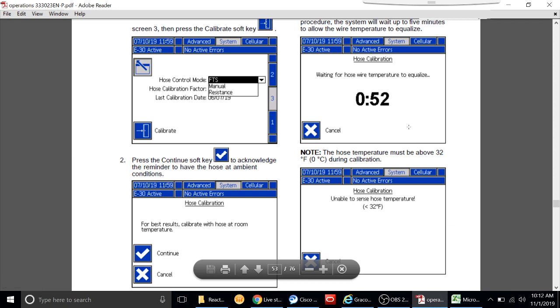You may see a window pop up here that gives you a countdown or a timer while the system is calibrating. But what happens if my system doesn't calibrate? What could be causing that? What would prevent me from running that? Well, a lot of times there's a connection within the hose that's not being made, whether it's an actual connection point or internally the wire wrap around that hose is broken. And if we're trying to figure out that value for the hose and there's no way of receiving a signal all the way through, you're going to get an error and it's not going to calibrate.